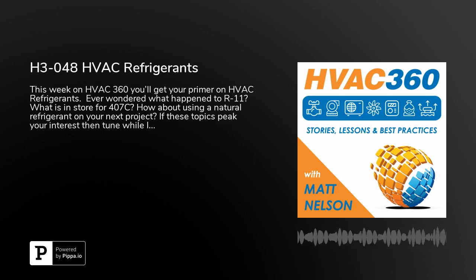If you go into a residential air conditioner, that will see very different, maybe not super different, but somewhat different operating temperatures. And if you go into a supermarket system, which needs to provide freezing of frozen pizza, frozen veggies, and ice cream in their display cases, that uses a completely different operating temperature for their system. So for each of these systems, we have traditionally had specific refrigerants that give us optimum performance.